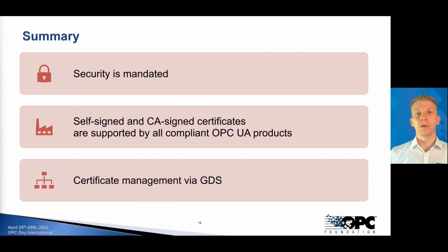And also a very important detail: there's no way around this certificate management, so you need to make yourself aware of it because security is mandated in OPC UA. Now, in the past, we had some exceptions for really tiny resource-restricted devices which could not handle RSA operations. But now with ECC built into the standard, those exceptions are not valid anymore, and therefore security is now required for all kinds of applications out there.